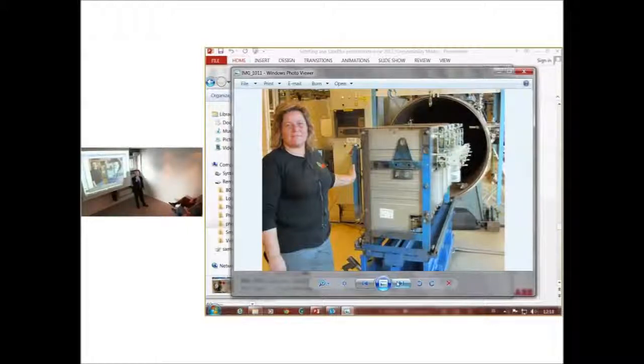Helium molecules are much smaller than SF6 gas. So then we measure with electronic devices, because they can sniff helium much easier than SF6. SF6 will stay on the sidewalls, it's more like water droplets. So helium is floating free around. We measure the helium for a certain time, and if we have no diffusion, then we make a new vacuum and fill it with SF6 gas at 1.4 bar.